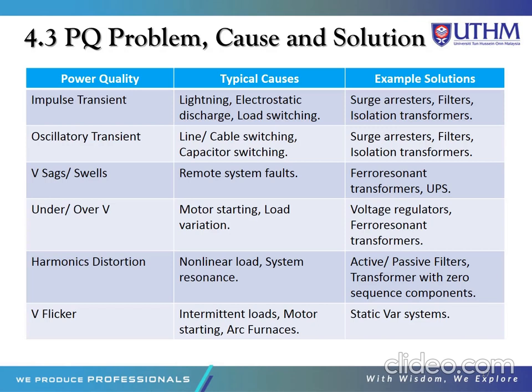Next we go to subtopic 4.3, PQ problems, causes and solutions. This is the power quality problems, the typical cause, and the example solutions. First, impulse transient. The typical causes are lightning, electrostatic discharge and load switching. The example solutions are surge arrestors, filters and isolation transformers. Second is oscillatory transient. The typical causes are line or cable switching and capacitor switching. The solutions are surge arrestors, filters and isolation transformers.